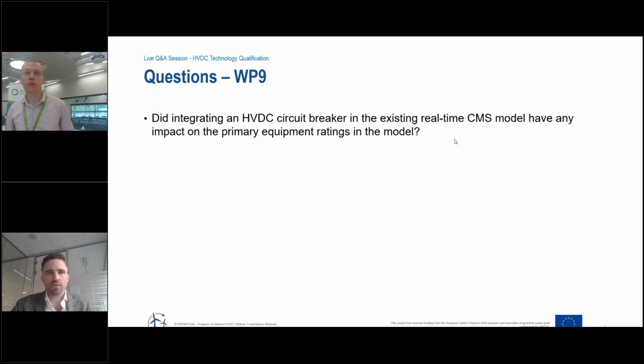Okay, that's really good news. So it sounds like there's an indication that an HVDC circuit breaker and the protection system could be added to a DC grid as an afterthought, as part of an expansion, for example. But of course, it has to be studied more deeply. Yeah, and I think it would require some control changes. As we know, the controls are a minor part. It's not building things and putting bigger platforms in or anything like that. So yeah, all good news. Not a big capex investment.